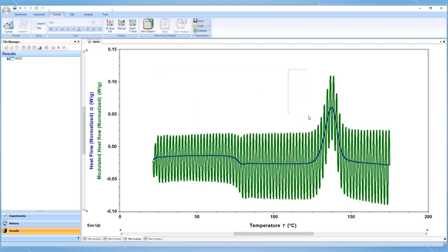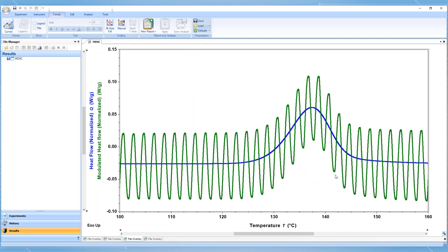The modulation period should be long enough to allow for a quantitative measurement of heat flow between the sensor and the sample. Too short a period may be too fast for the sample to maintain the desired modulation, which will result in poor data. Too long a period will require a lower average heating rate to achieve the appropriate number of modulations required.